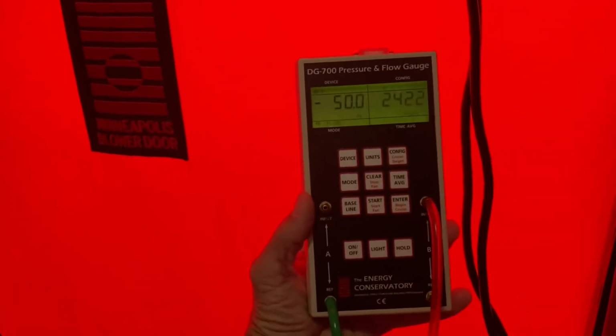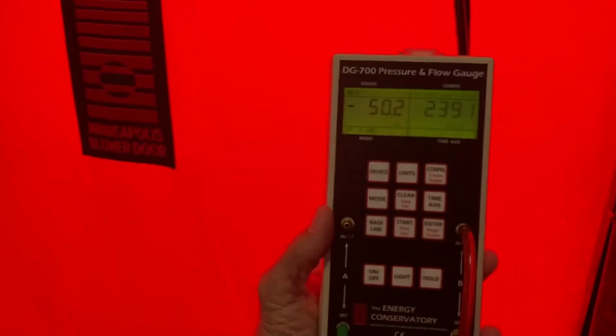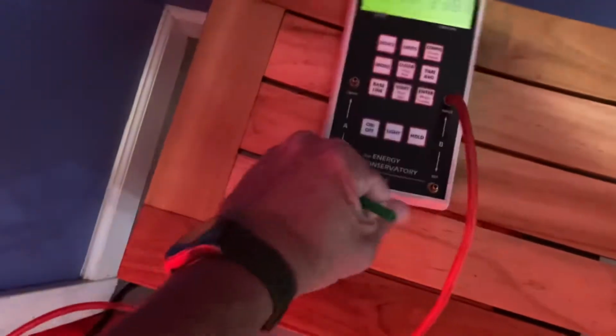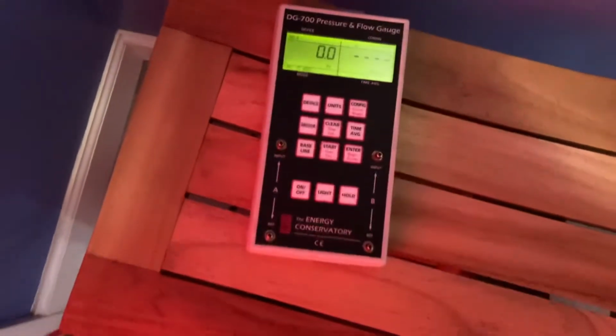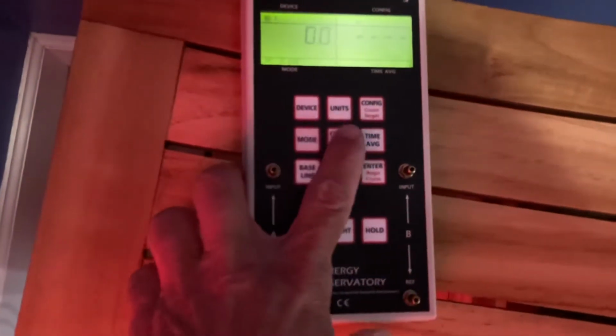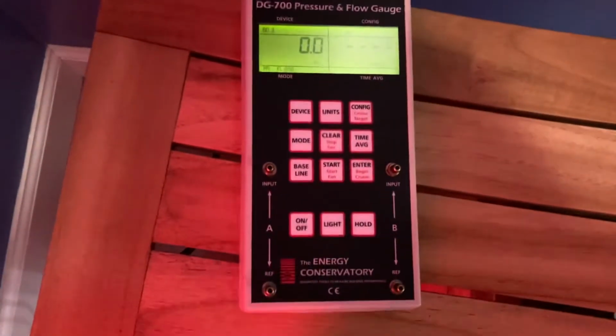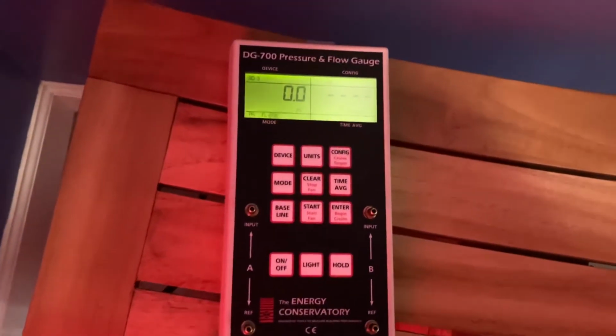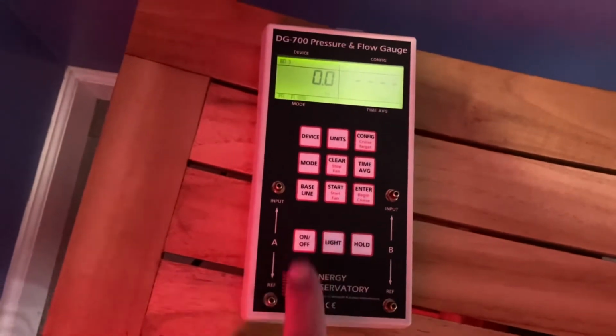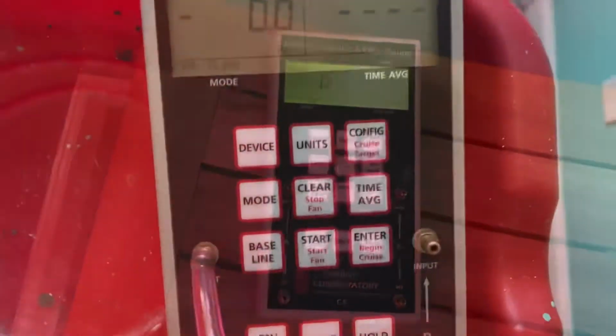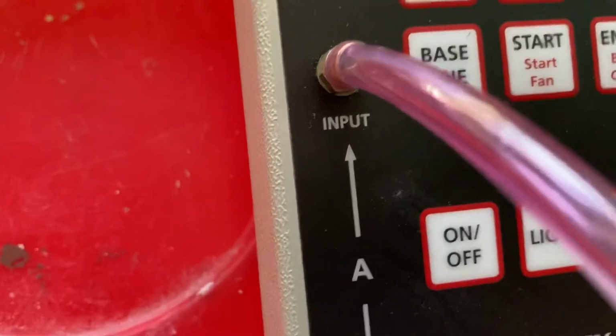DG700, pretty much the same setup. You get your house to 50, pull your hoses, clear your baseline reading, and then it'll be at zero. You can also just turn the DG700 on, off, and then on again, and it'll be recalibrated for that setting. Hook it to your input on your A channel, back to the hood, put it against the ceiling, and it should read pretty much what the 1000 read, pretty close.